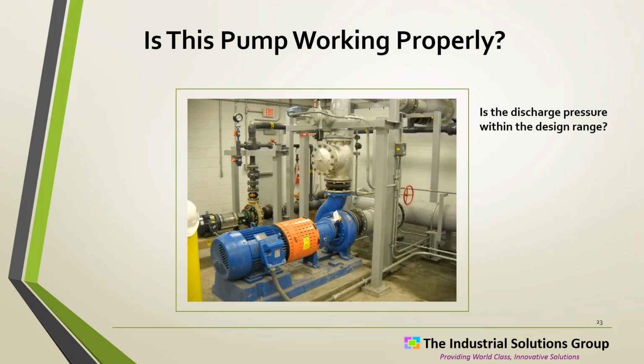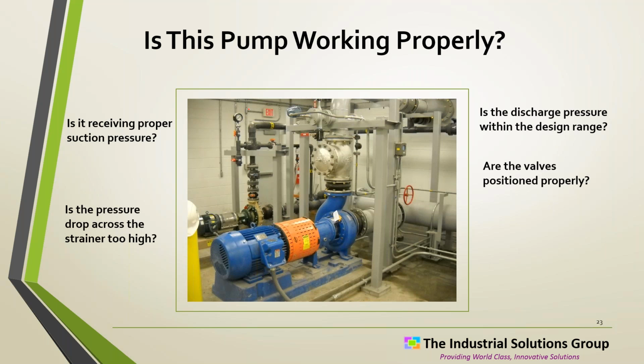And before you answer yes, here are some questions. Is the discharge pressure within the design range? Is it receiving proper suction pressure? I don't see any pressure gauges here. I can see a couple of pieces here and there, but can you really answer all the questions? Is the pressure drop across the strainer too high? Are valves positioned properly? Are there limit switches on valves? Is the right amount of flow being circulated? There's not a flow meter here, maybe somewhere else in the system.